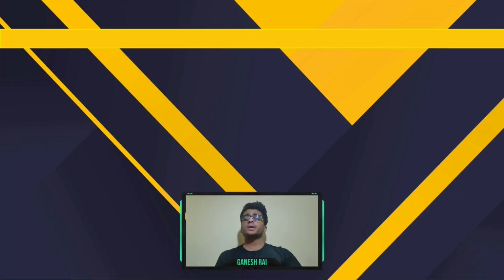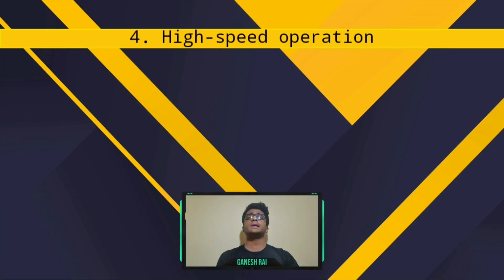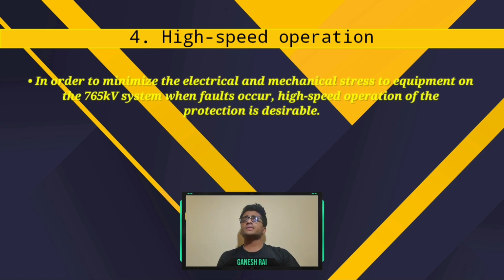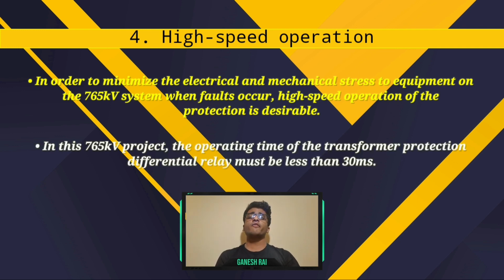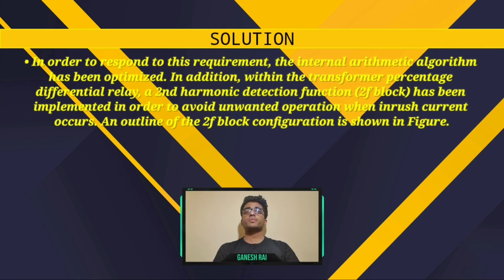Now talking about the high-speed operation of this protection relay. In order to minimize the electrical and mechanical stress to equipment on this 765 kV system when a fault occurs, high-speed operation of the protection relay is desirable. In this 765 kV project, the operating time of the transformer protection differential relay must be less than 30 milliseconds. In order to respond to this requirement, the internal arithmetic algorithm has been optimized.